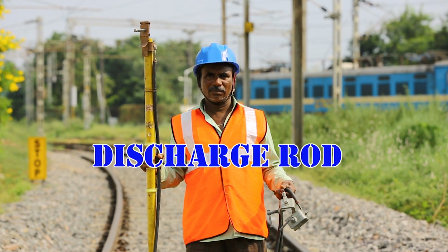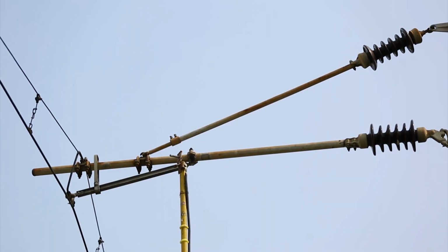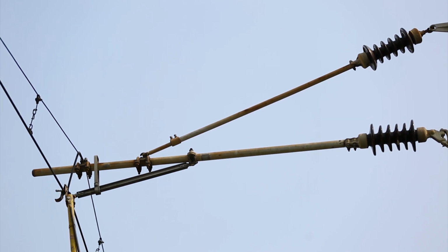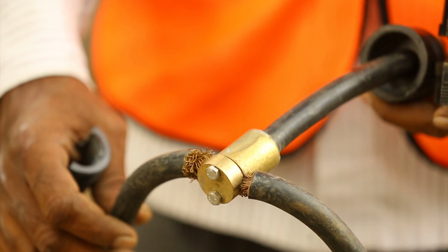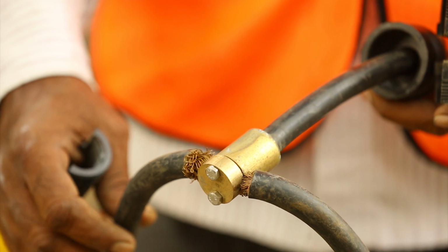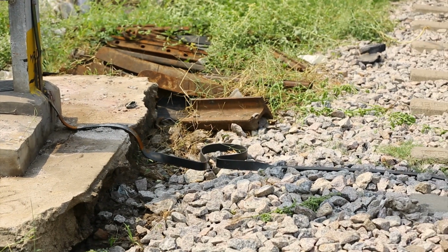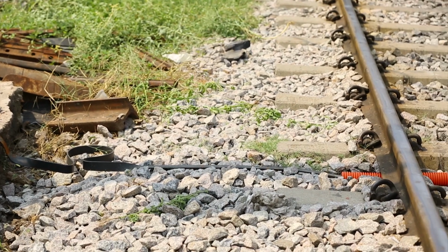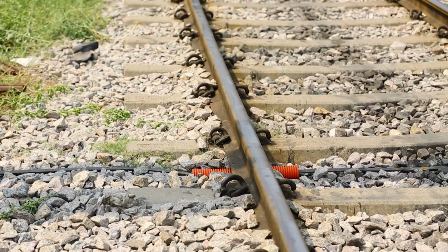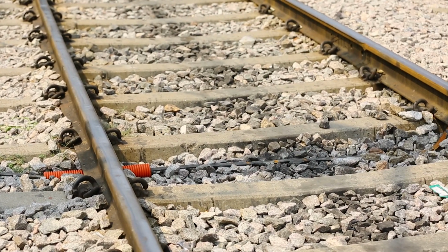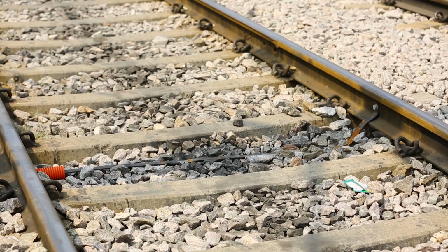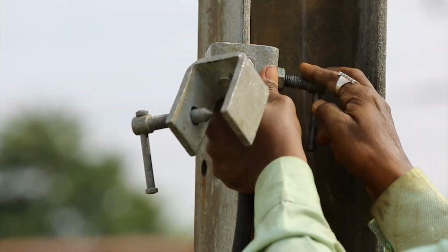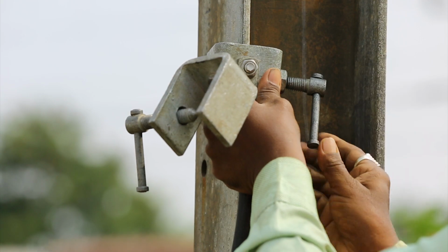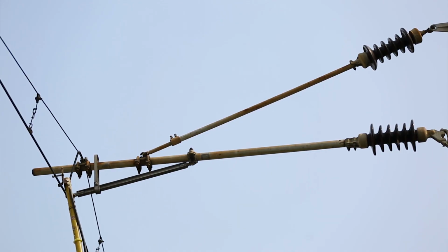Discharge rod. When OHE is shut down, then a discharge rod in good condition is provided on dead OHE to earth the induction effects. It is important to make sure that cable strands are intact and structure bond is in good condition. Discharge rod is clamped onto the mast and held onto the contact wire.